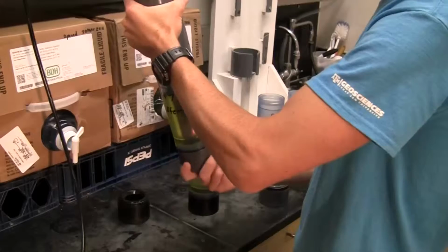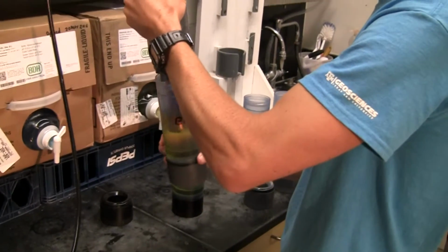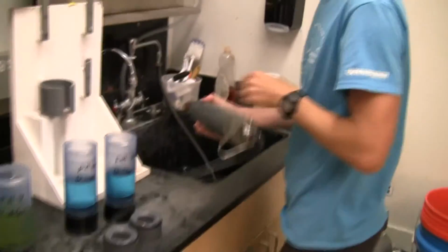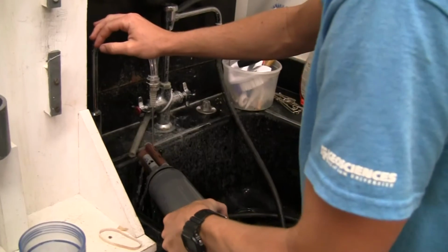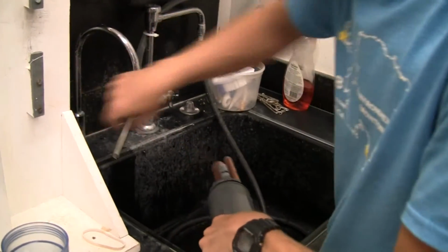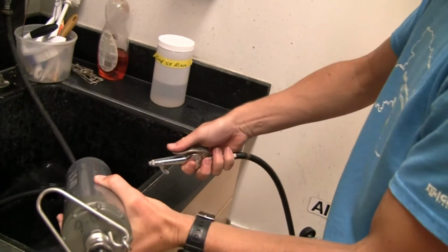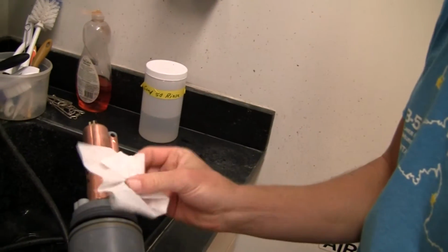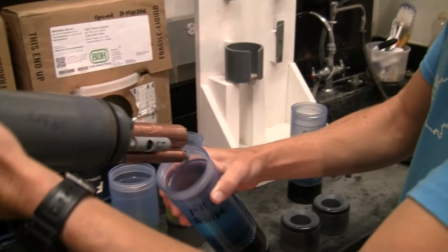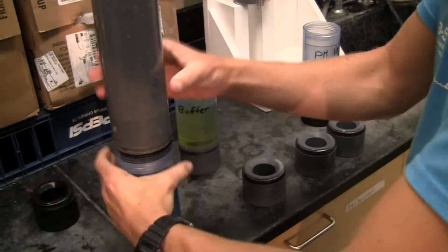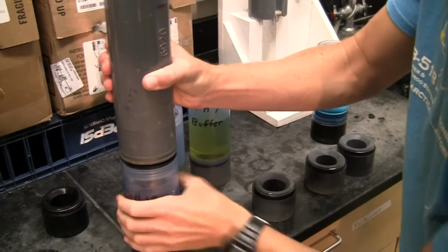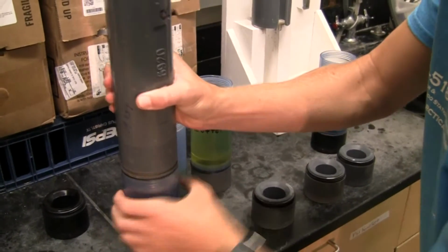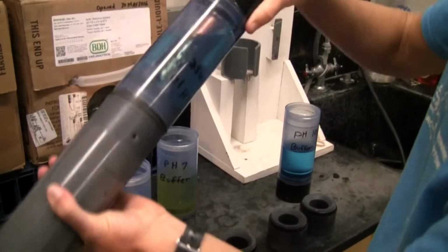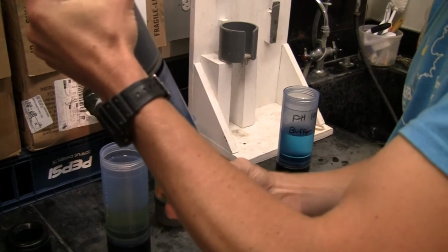So now we go back to the unit. We remove the 7 buffer. Now we rinse and clean the unit with DI water and compressed air, and if required, a Kimtech wipe. So now we place the sensor head in the pH 10 rinse. Screw the cap down so it doesn't leak on the table. Thoroughly rinse the sensor head. Unscrew and place in the pH 10 buffer.